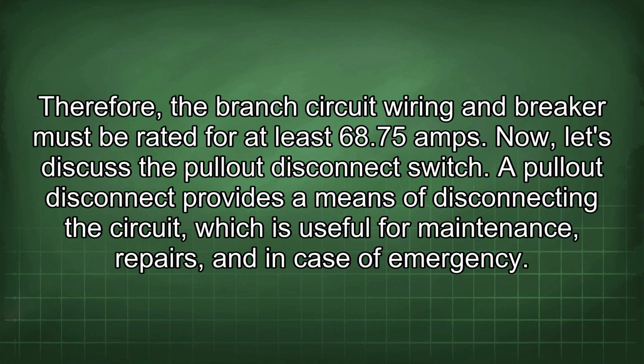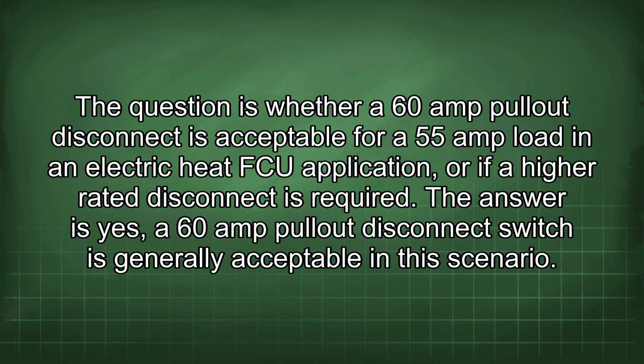Now let's discuss the pull-out disconnect switch. A pull-out disconnect provides a means of disconnecting the circuit, which is useful for maintenance, repairs, and in case of emergency. The question is whether a 60 amp pull-out disconnect is acceptable for a 55 amp load in an electric heat FCU application, or if a higher rated disconnect is required. The answer is yes, a 60 amp pull-out disconnect switch is generally acceptable in this scenario.